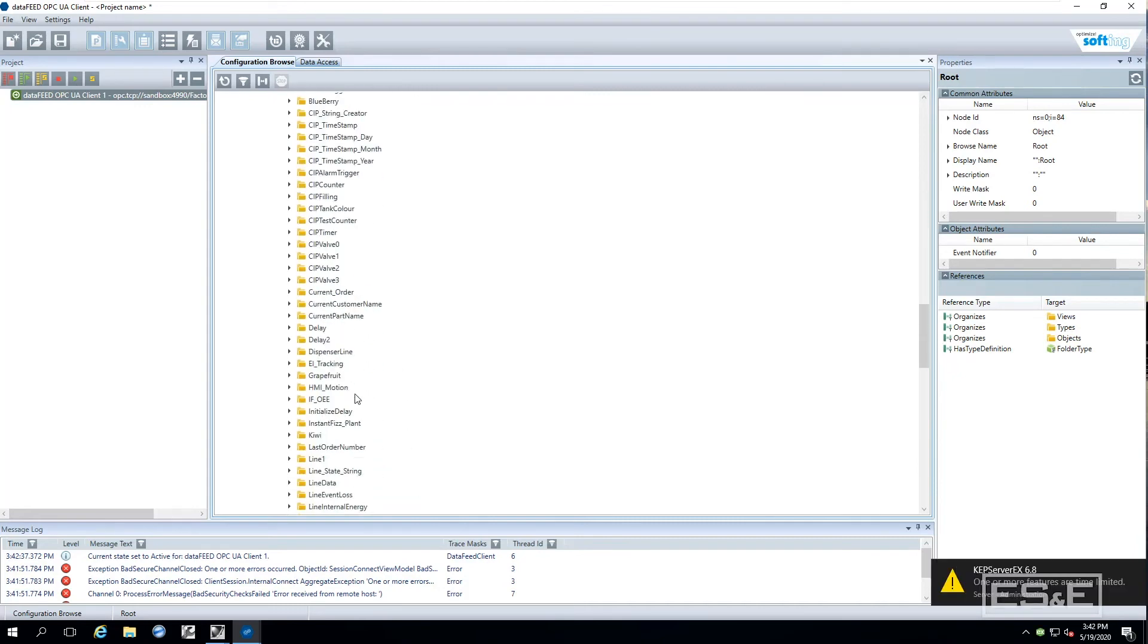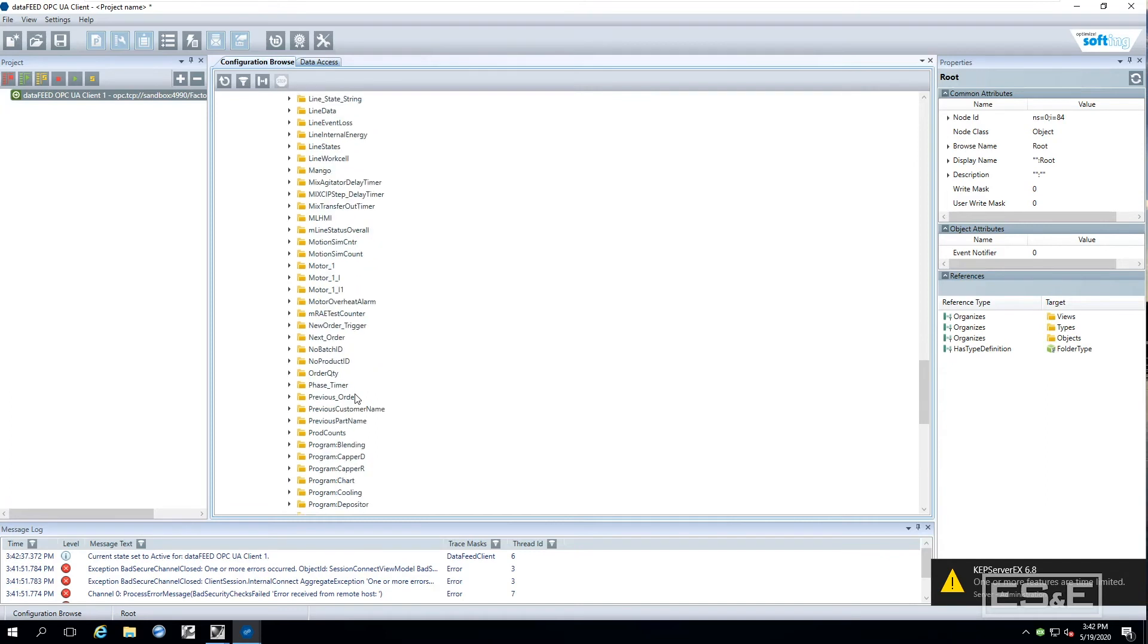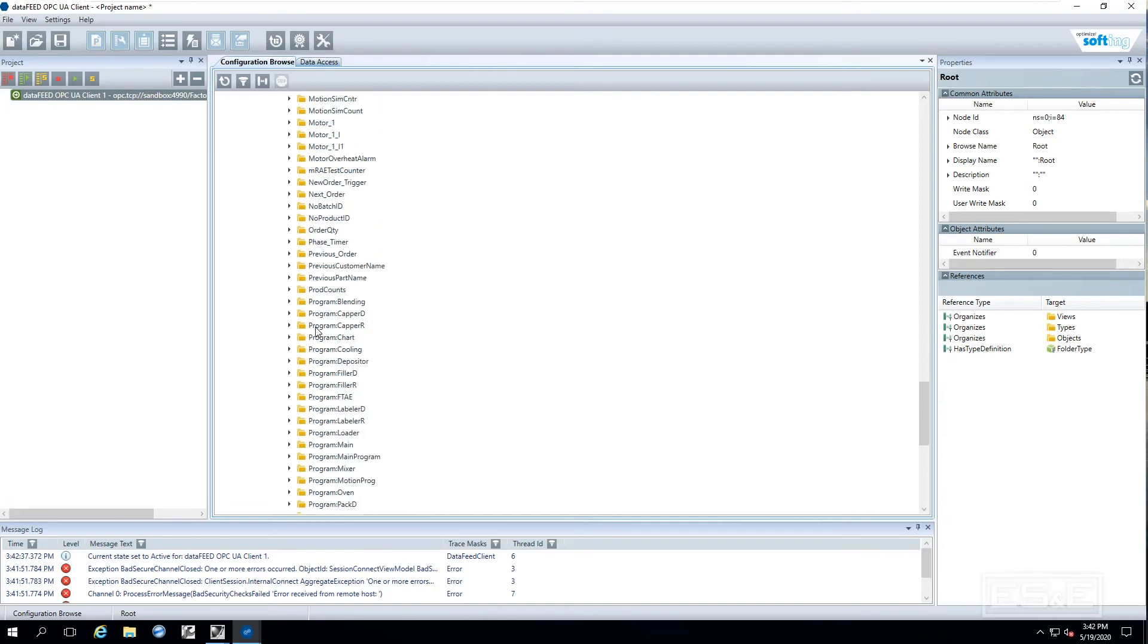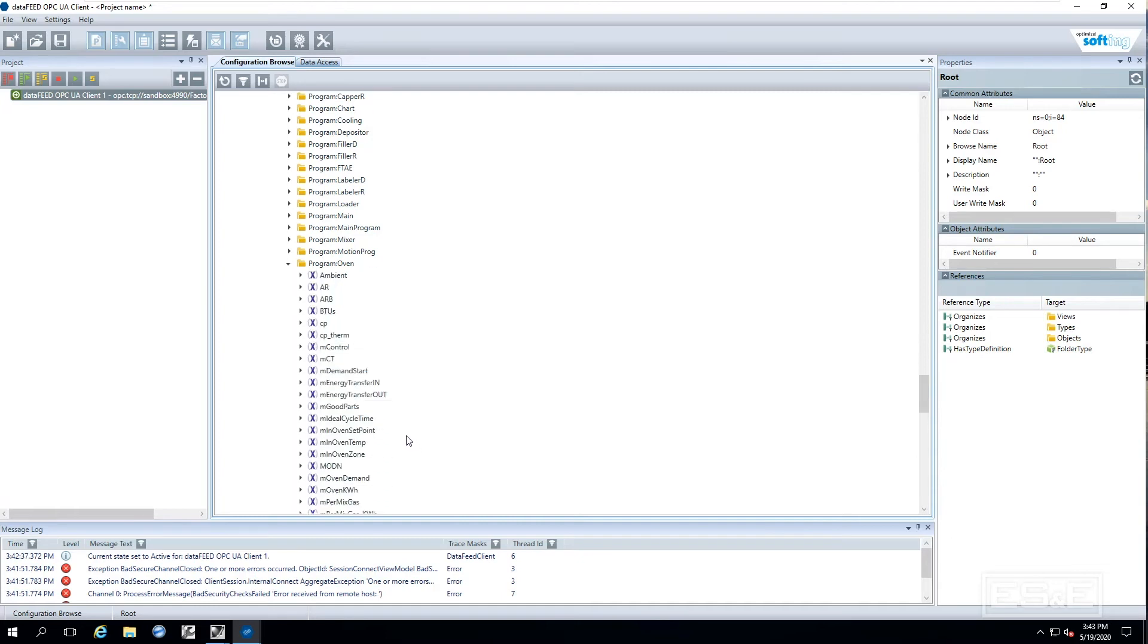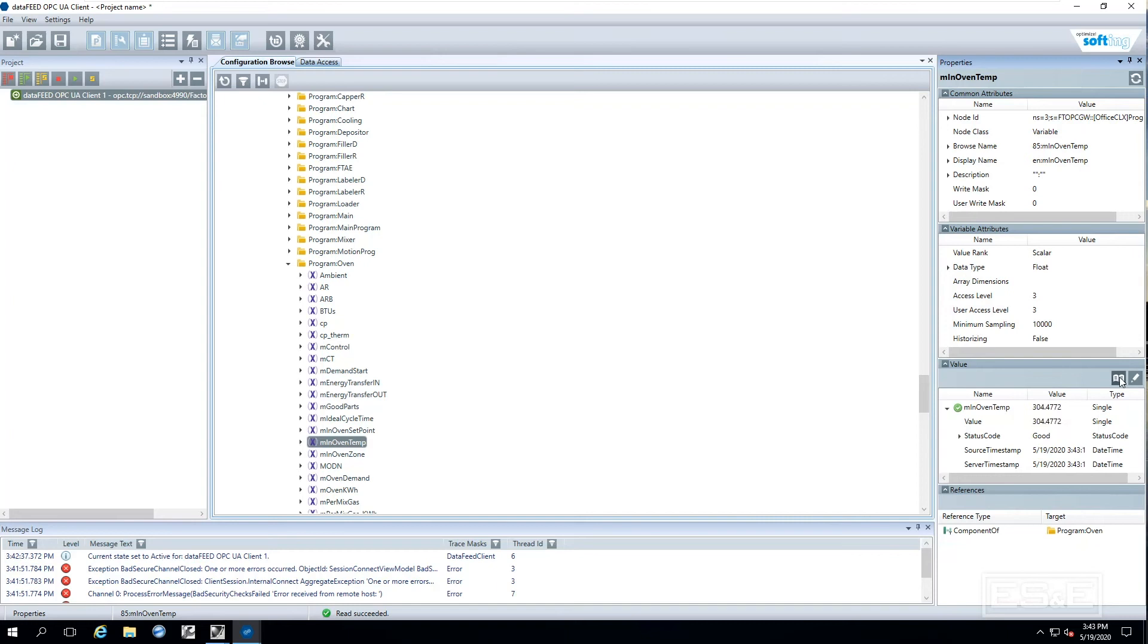So what is happening at the end of the day is our FactoryTalk Linx is communicating with controllers, putting it into factory talk services and now this factory talk gateway is connecting to the services and exposing those tags through an OPC UA connection and it is allowing that client. You can see we are updating. So that is all there is to setting it up.